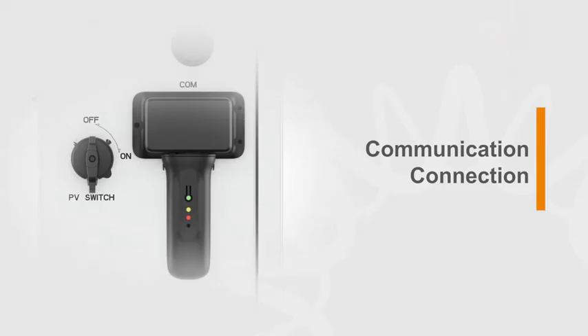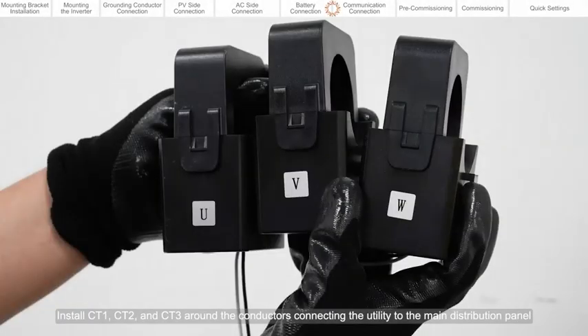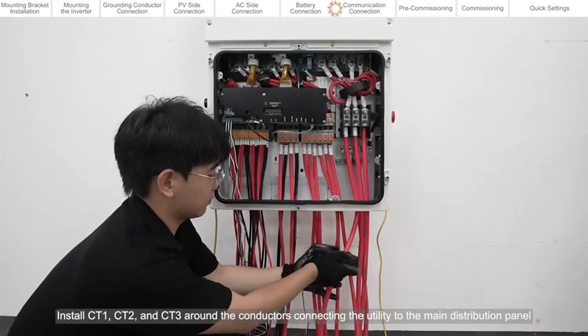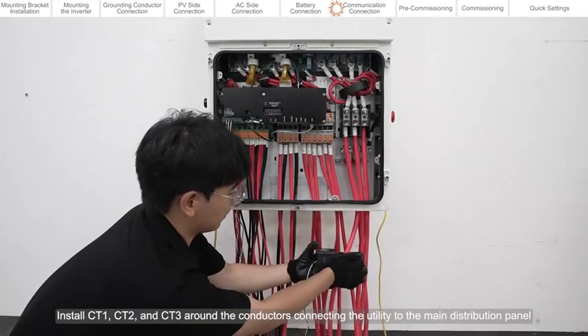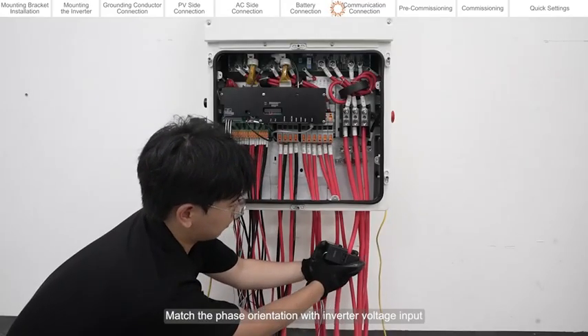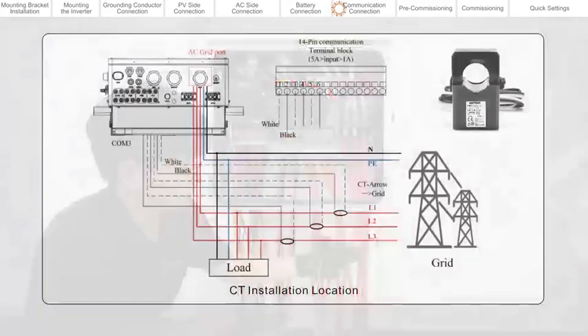Communication connection. Install CT1, CT2, and CT3 around the conductors connecting the utility to the main distribution panel. Match the phase orientation with inverter voltage input.